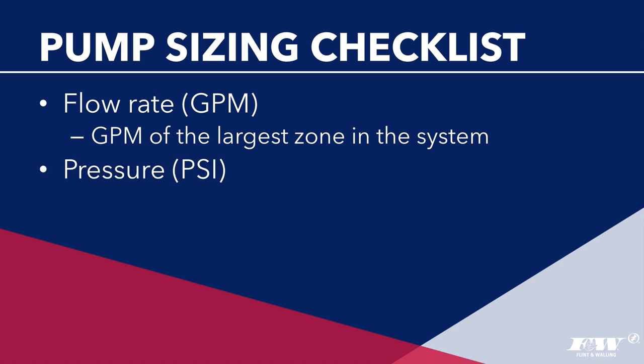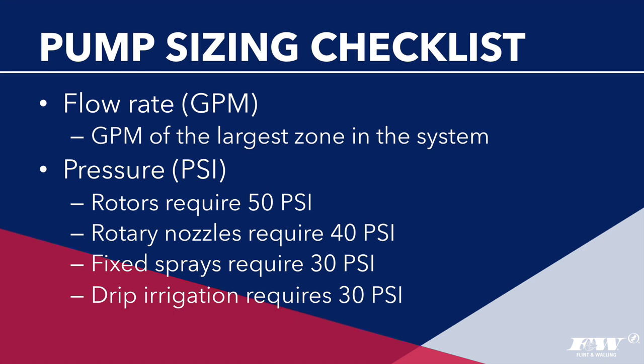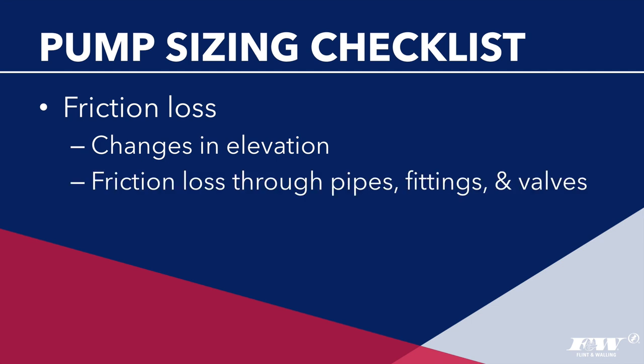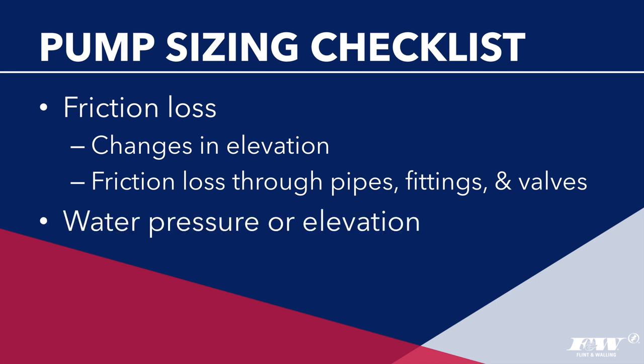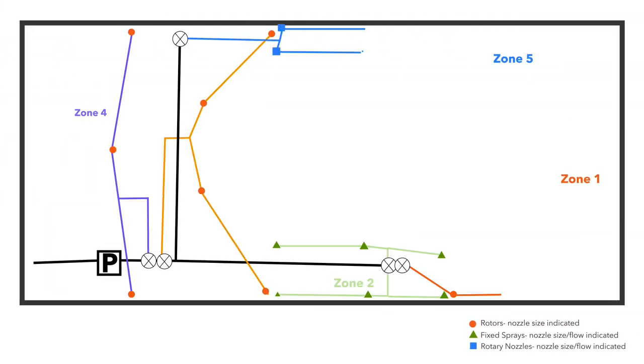For the flow rate, you need the GPM of the largest zone, or the maximum flow rate the system will use at any one time. For the pressure, you need the pressure required at the sprinklers — in residential systems, rotors typically require 50 PSI, rotary nozzled sprinklers 40 PSI, fixed sprays 30 PSI, and drip irrigation zones 30 PSI. You'll also need the friction loss between the pump and the sprinkler with the greatest pressure loss, including elevation changes to the highest point, friction loss in pipes, fittings, and valves, and the pressure or elevation of the water coming into the pump (city pressure or suction lift).